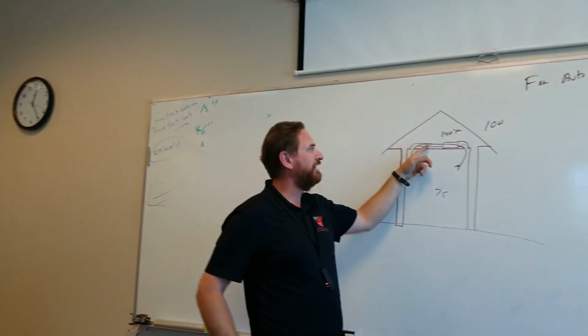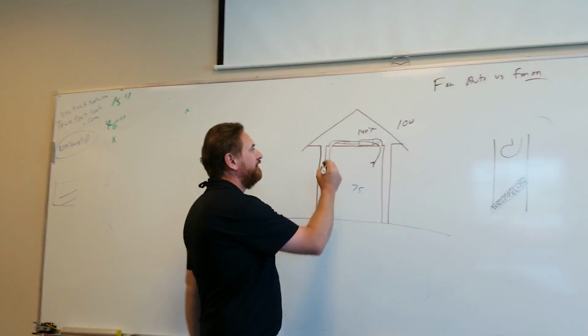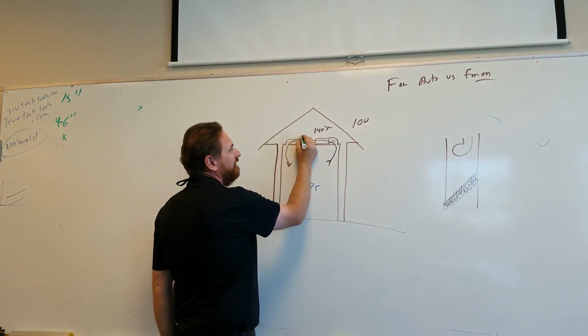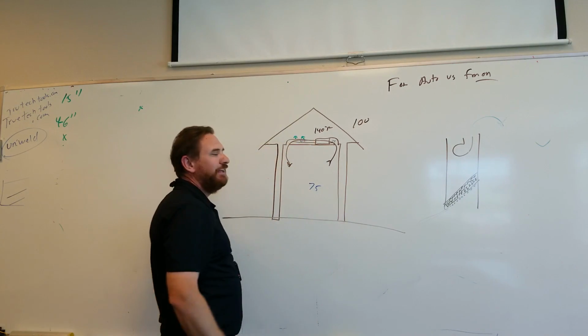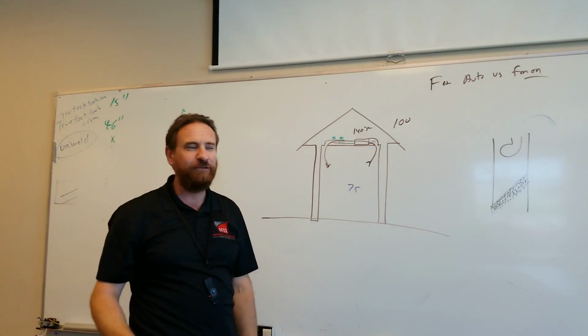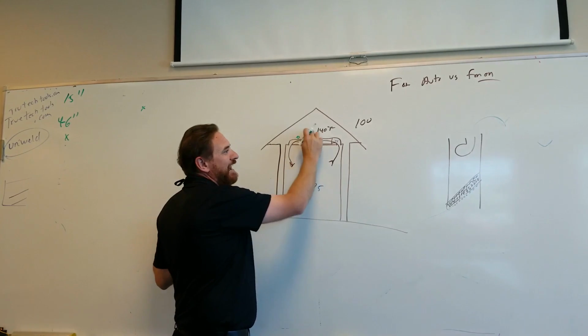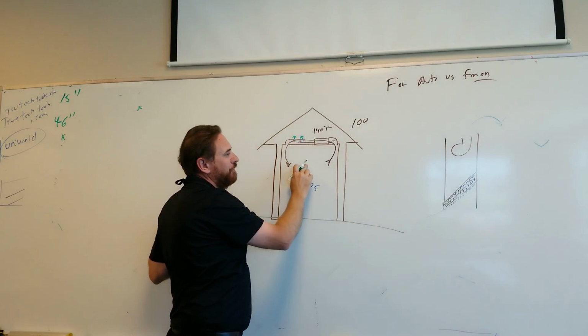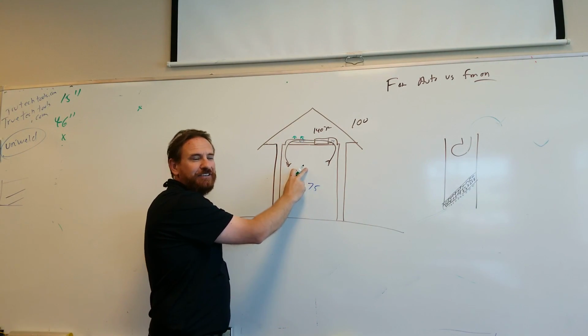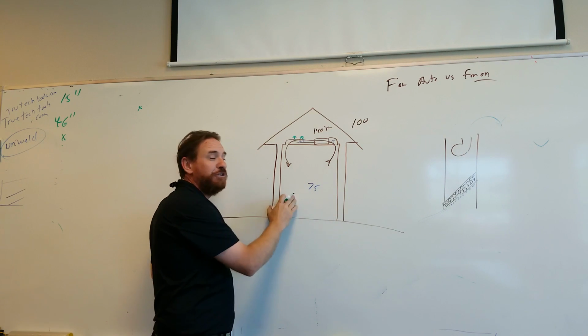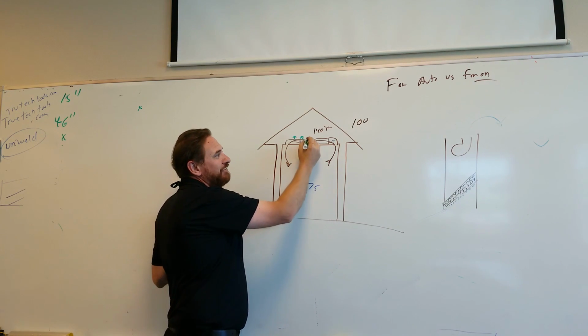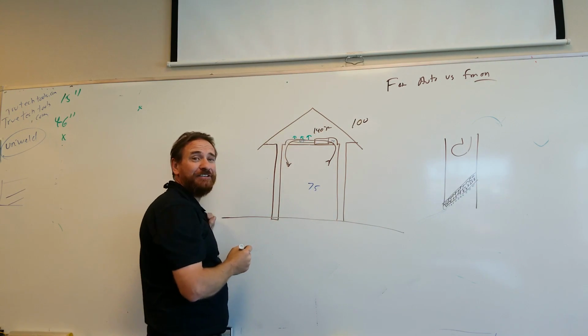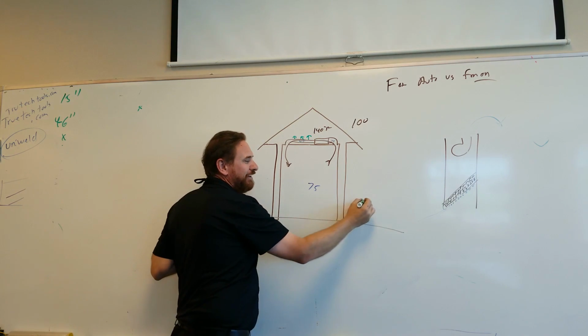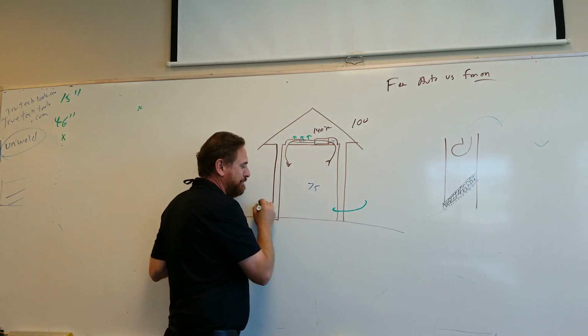One other thing I forgot to mention was loss. Let's say we have leaking ductwork. So if I have the air that's leaking outside the duct system, that's an immediate energy loss directly. But as I take air out of this room, then I have to worry about depressurizing the house. So the pressure of the air outside is greater than the pressure inside because the fan's literally pushing some of the air out of the house into the attic. Well, then the pressure outside has to bring air from outside back in.